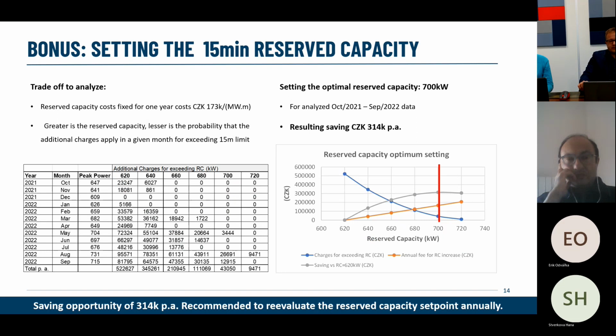And I did such analysis, you see on the next slide. So I look at the data every month. What was the peak power? How much did we exceed the limit of 620? And the column at 620, that's the current limit. Okay, so it means that they paid more than 500,000 Czech crowns for spending above that 620 limit. And then I did a sensitivity analysis. So if I increase the reserve power to 640, 660, etc., and as you can see, if I set it to 720, there was just 1 month when they exceeded.